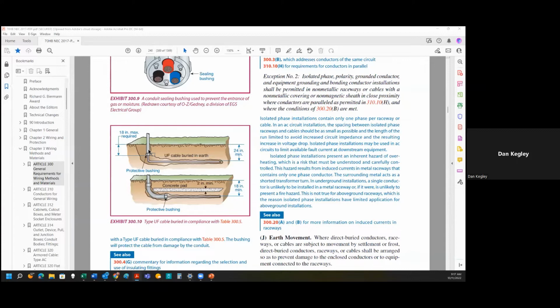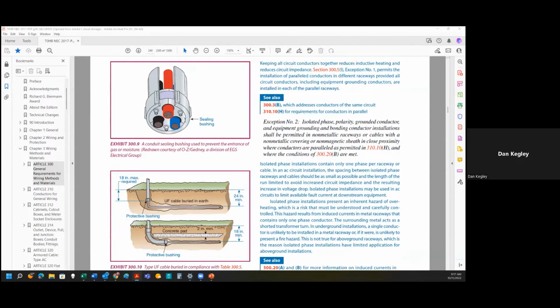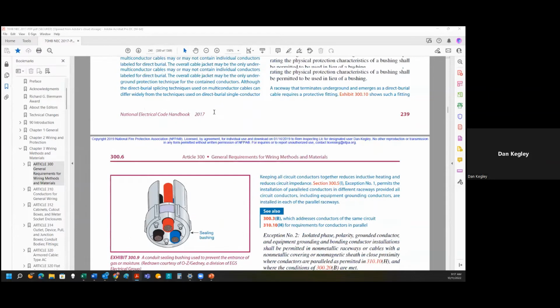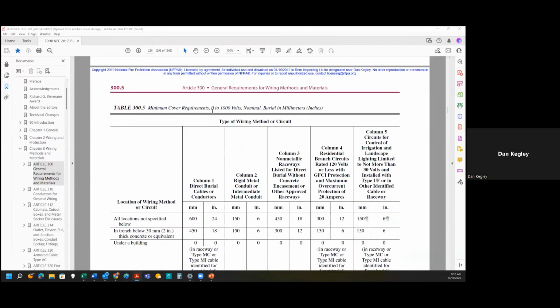Yep. One question that did come up is, does the burial depth apply to both high voltage and low voltage wire? So let's just say we're running an alarm wire for a holding tank. Does that 24 inches or 18 inches apply to those wires as well? It does. If we go back up to this chart here, it says 0 volts to 1,000 volts. Okay, so even if there's 0 volts in that cable, it applies to that cable. Gotcha. Yep. So when you say low voltage and high voltage, whether it's a 12 volt or 24 volt control circuit, or if it's a 120 volt line circuit, or a 240 volt pump circuit, this is 0 to 1,000 volts. Gotcha.